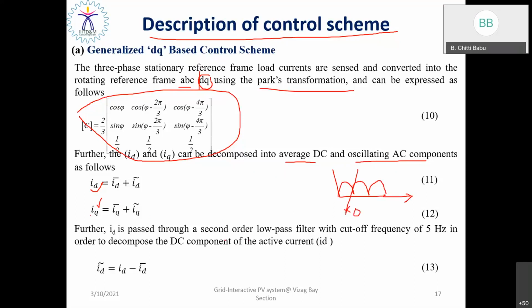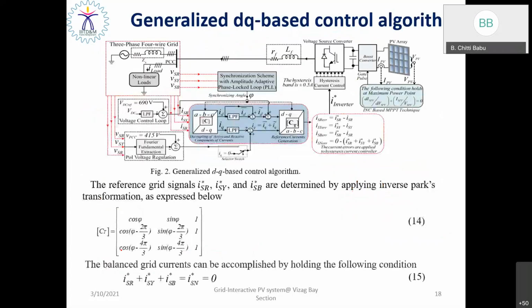So we use a second order low pass filter for ID with a cutoff frequency of 5 Hz, so that we can extract the DC component of the active current, which is responsible for active power control. And this is the DQ based control algorithm, where the PV array feeds power to the DC link capacitor via the boost converter. Then the DC will be inverted into AC, and the AC power that is available can be injected into the utility grid via the filtering inductor or interfacing inductor.